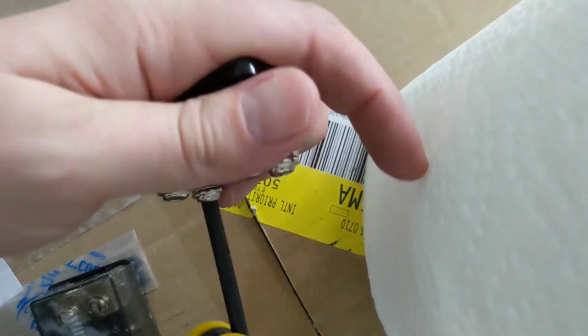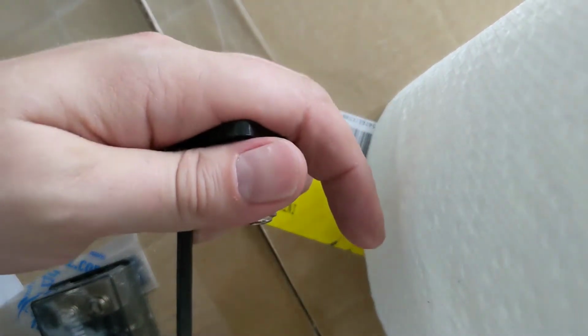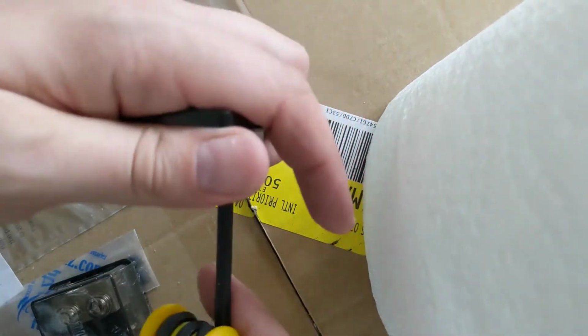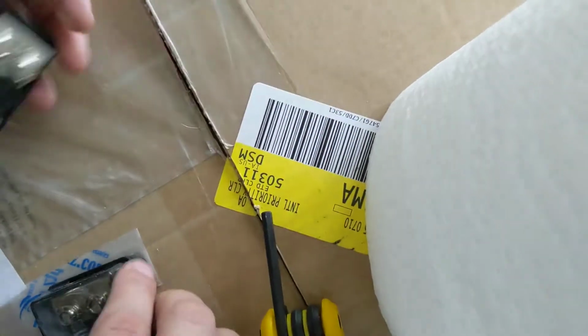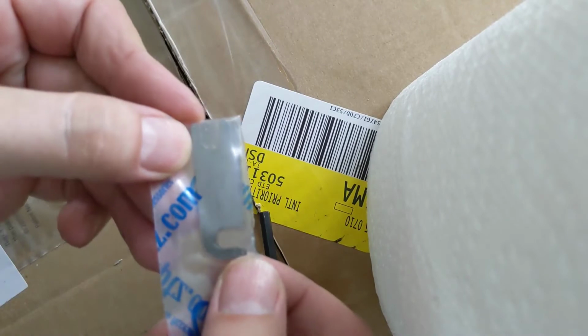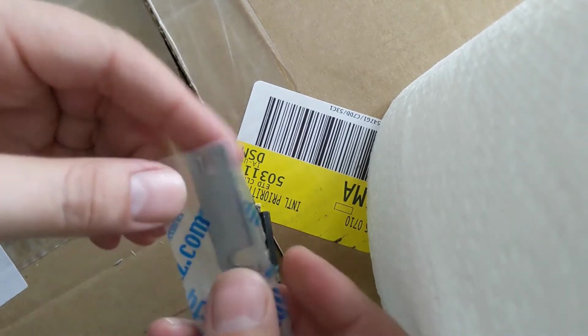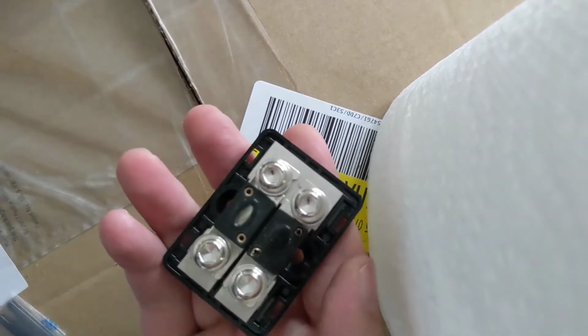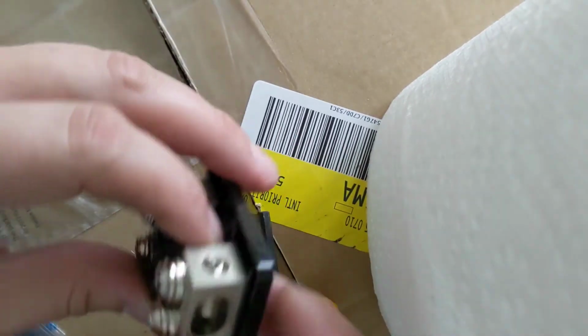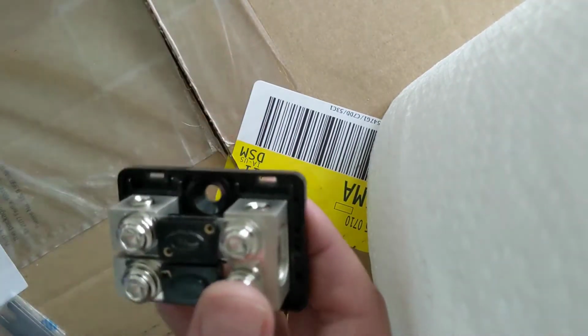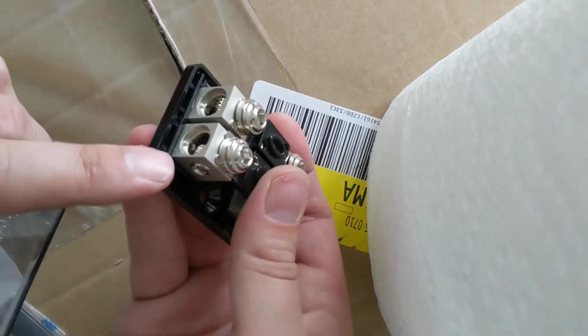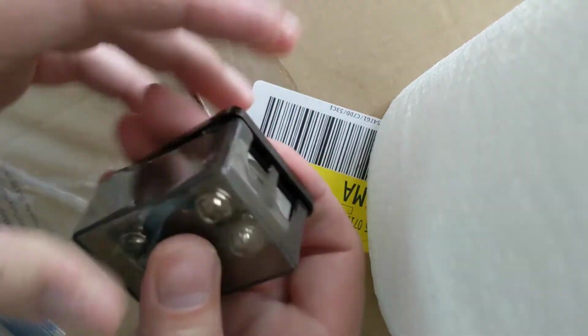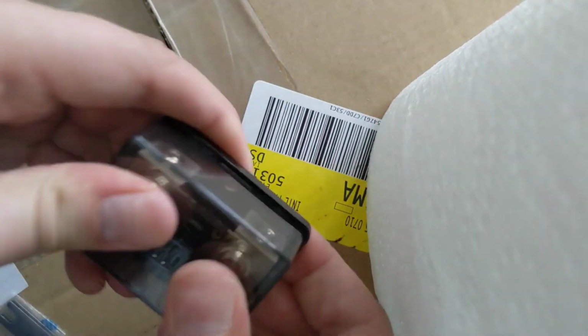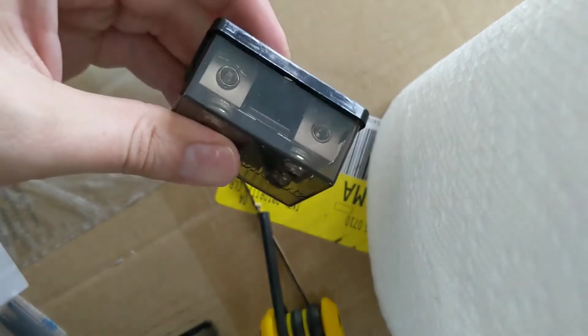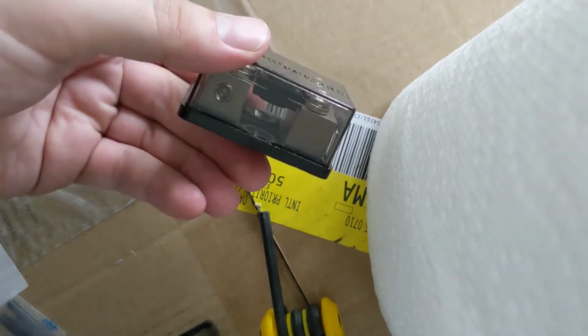Putting in the other distribution block, which is for my ground side, you assemble it the same way. The only difference is you use flat bar links instead of fuses. So you've got your assembly there, put in your cable, bolt in from the side. Once you've done that on all the applications, snap your cover back on, and you've got a pretty inexpensive fused bus system.